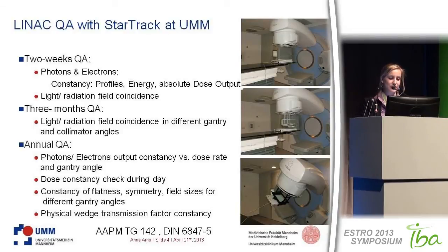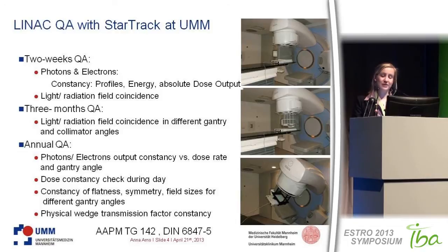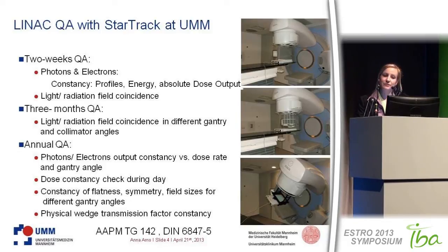The linac QA we perform with Star-Track at our clinic is the two-week QA. We mostly focus on light and radiation field coincidence, and of course the profiles, energy, and absolute dose outputs from various gantry angles and from four different dose rates. You can either position the Star-Track on the couch or with a dedicated holder mounted on the gantry.